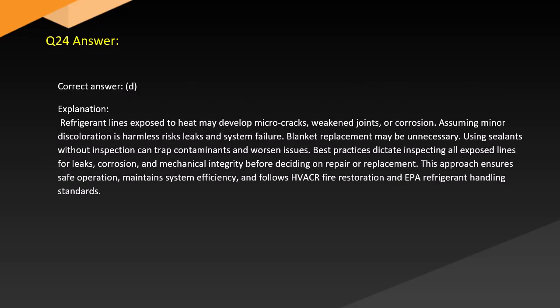Answer. Correct answer: D. Explanation: Refrigerant lines exposed to heat may develop micro cracks, weaken joints, or corrosion. Assuming minor discoloration is harmless risks leaks and system failure. Blanket replacement may be unnecessary. Using sealants without inspection can trap contaminants and worsen issues. Best practices dictate inspecting all exposed lines for leaks, corrosion, and mechanical integrity before deciding on replacement. This approach ensures safe operation, maintains system efficiency, and follows HVACR fire restoration and EPA refrigerant handling standards.